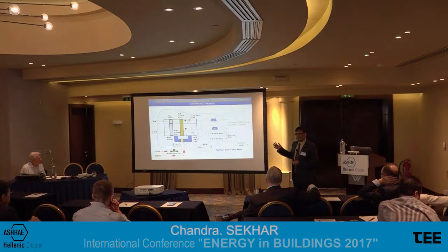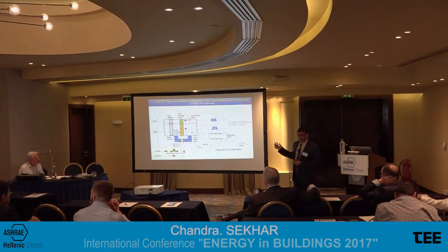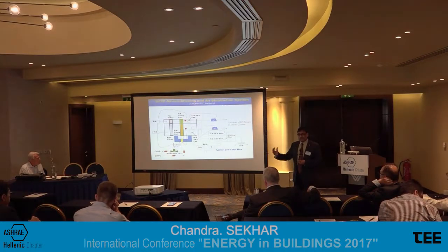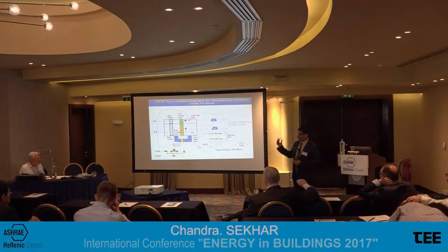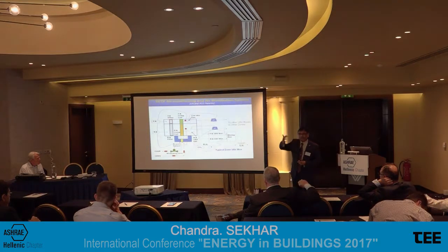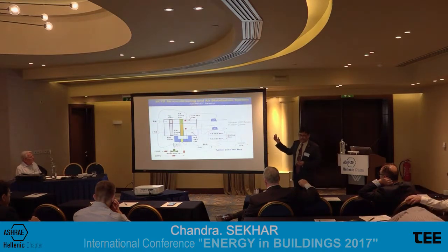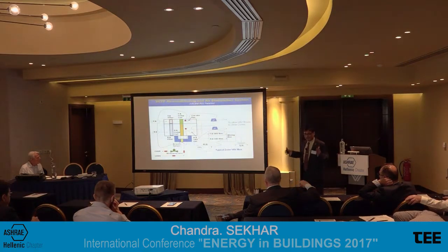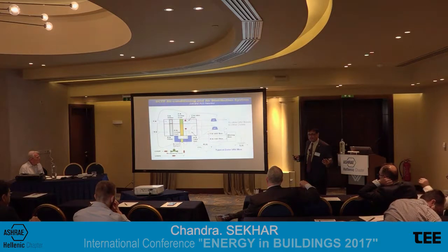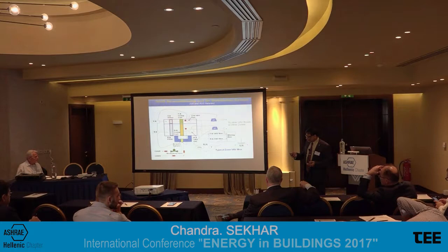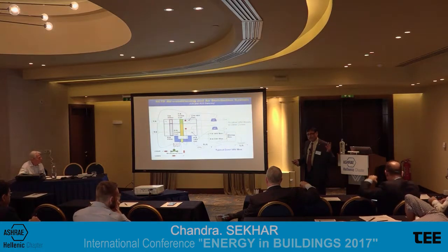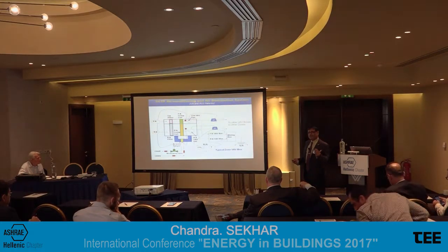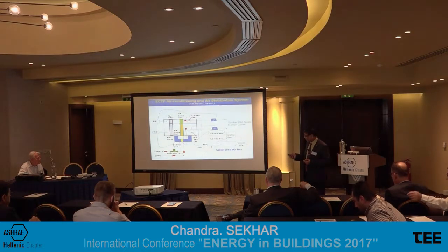Compare this with what happens in a typical demand ventilation system. You would place a CO2 sensor in the air handling unit return air, and that is going to be an aggregate, an average of what's happening in all the zones. Now, there are implications. We know for a fact that all the occupied zones don't behave in the same manner. Some zones may have high latent load, more occupants, some may have less, and this is a dynamic process. So wouldn't it be better if we took the demand ventilation concept right up to the occupied zone? That's the spirit of what we are trying to do here.